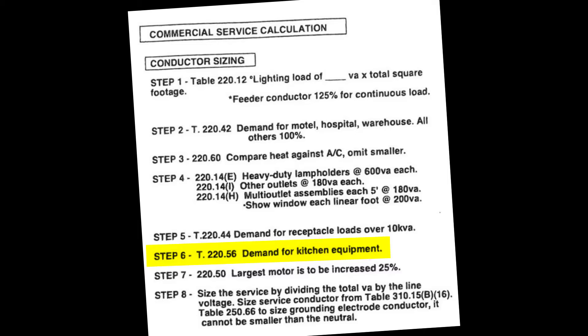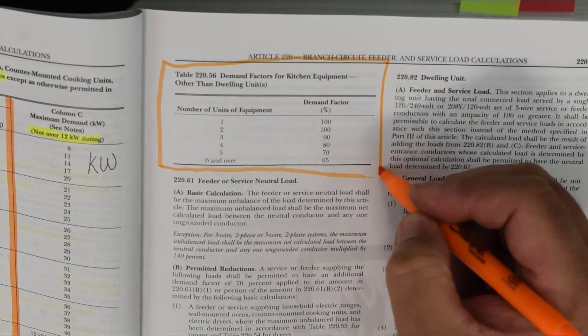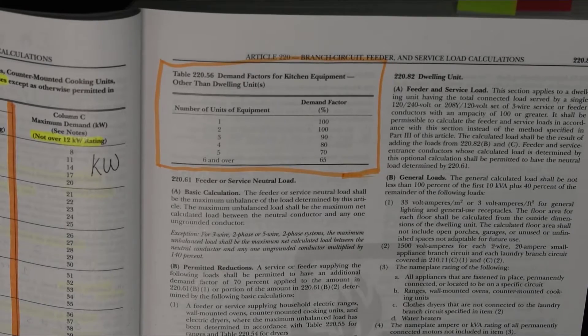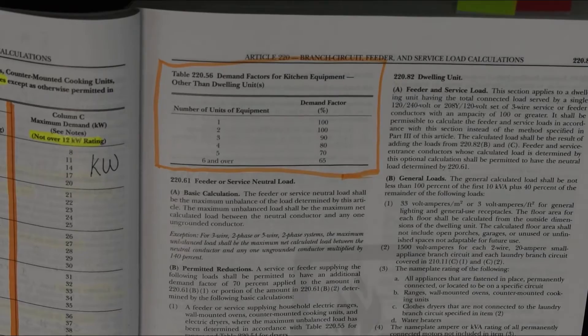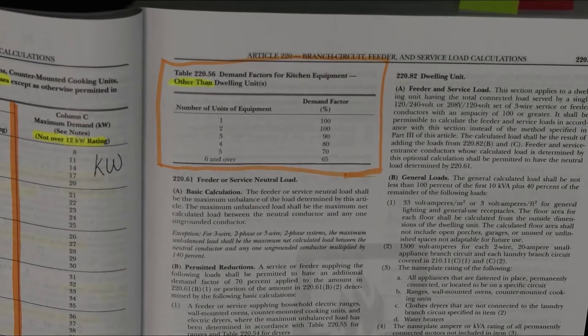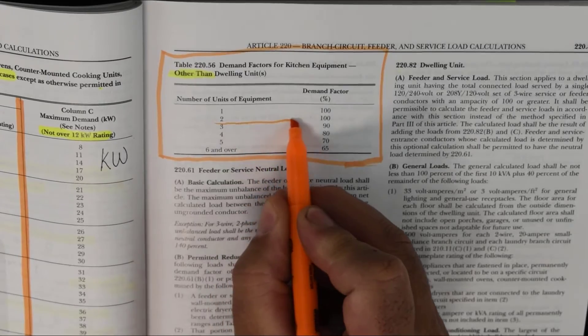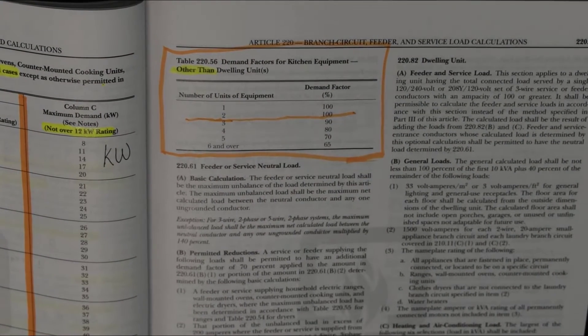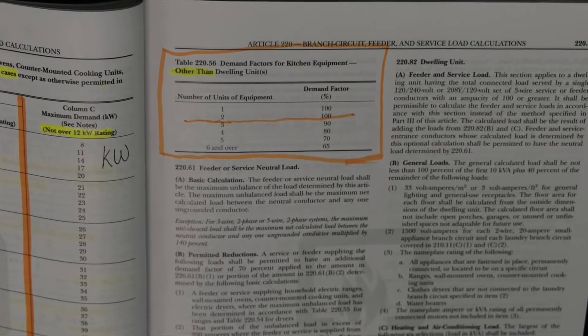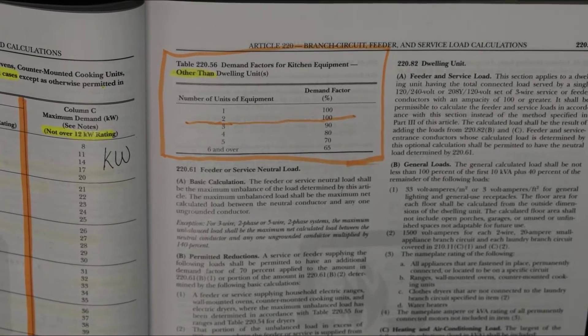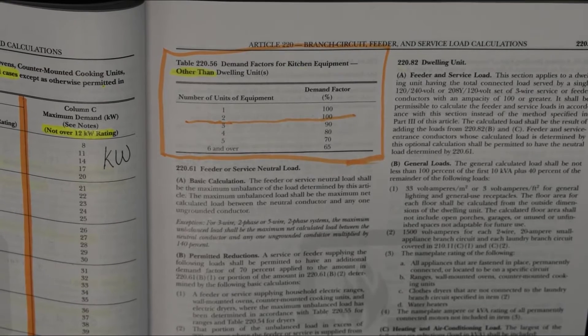Step 6 takes us to 220.56 and its table, covering demand for commercial kitchen equipment — specific only to commercial kitchens, not dwelling units. You add up the nameplates of all the different pieces of kitchen equipment. Once you get past two pieces of equipment, you start taking a discount. At six or more pieces of equipment, it's a 65% demand factor. This reflects the practical reality that in a commercial kitchen with 10 different pieces of equipment, you probably won't be using all of them simultaneously at full load capacity.